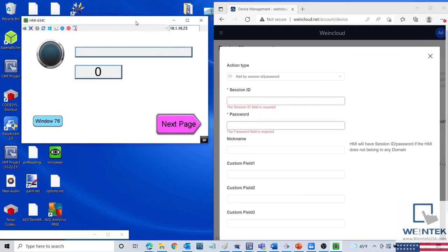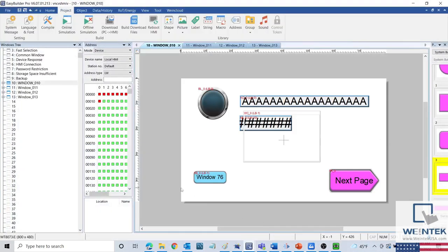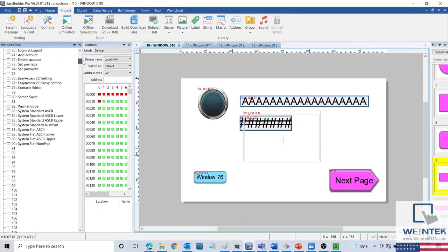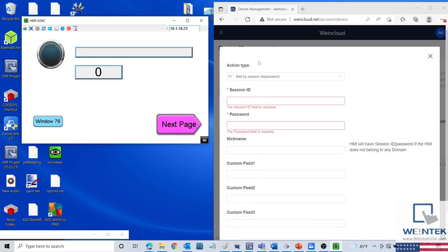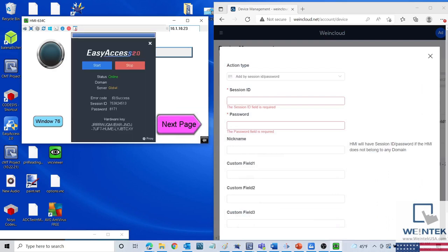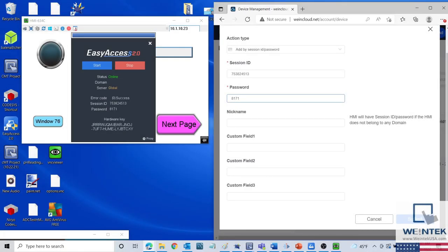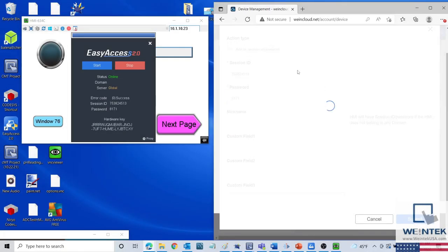For non-CMT HMIs, the session ID, password, and hardware key can be displayed using Window 76 within Easy Builder Pro. You will have to configure a project in Easy Builder Pro that will allow you to navigate to this window and view the session ID. Note that an HMI will need to be connected to the internet to get its session ID, and each HMI can only be registered to one domain at a time.